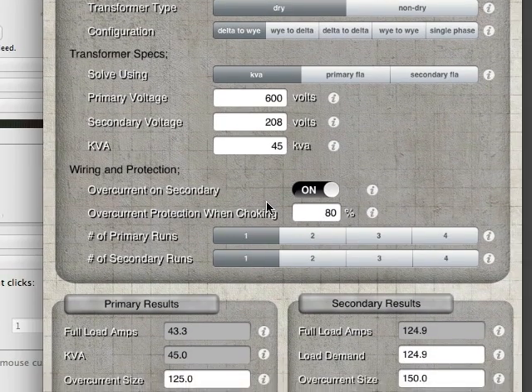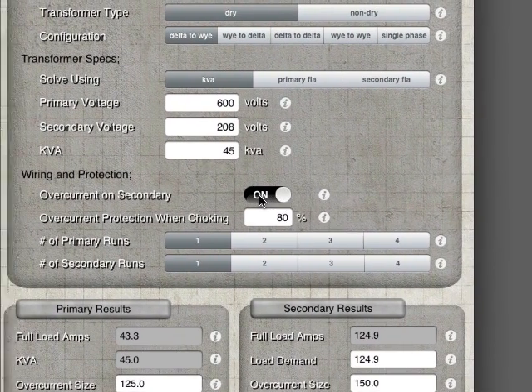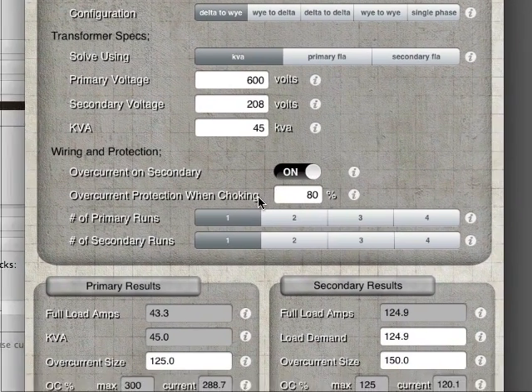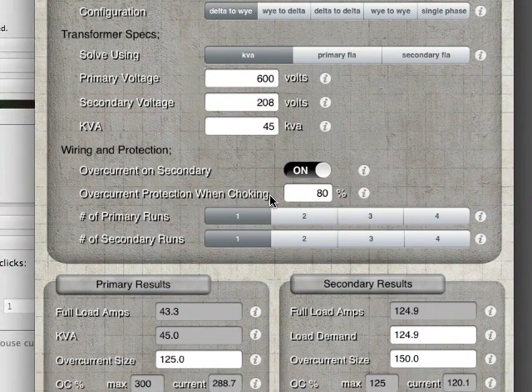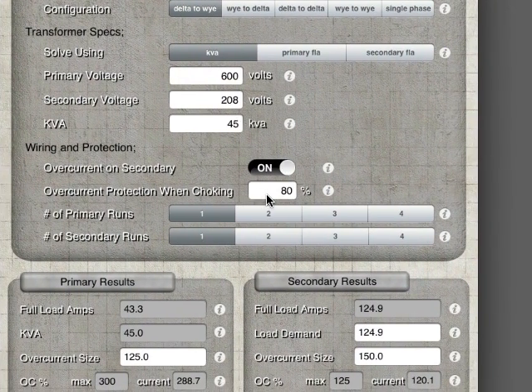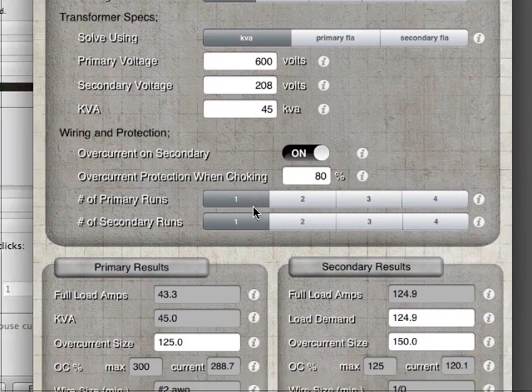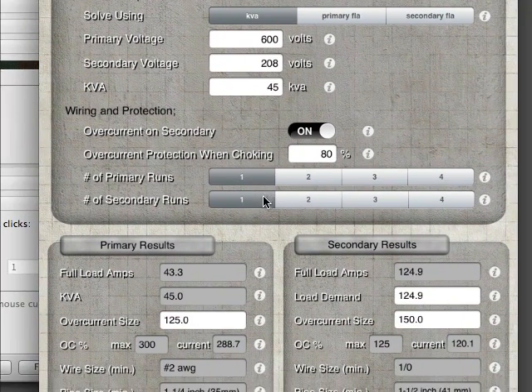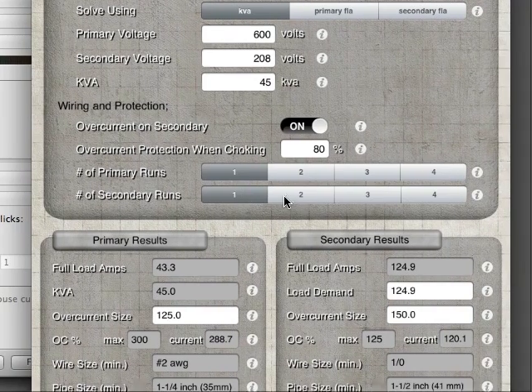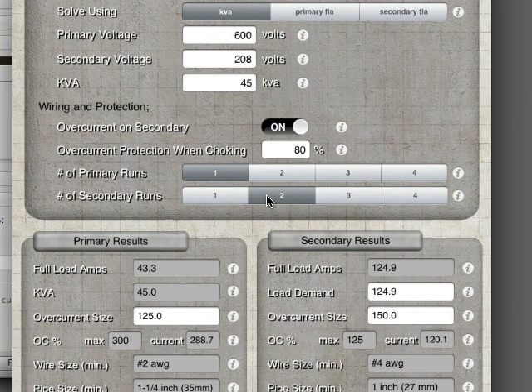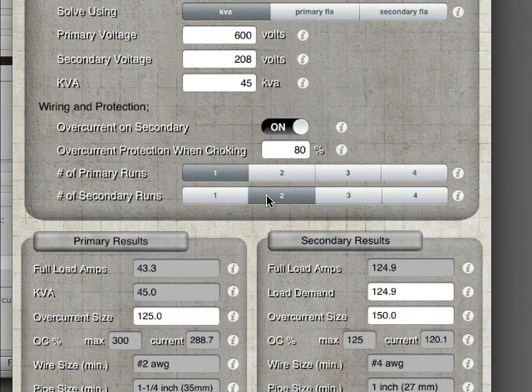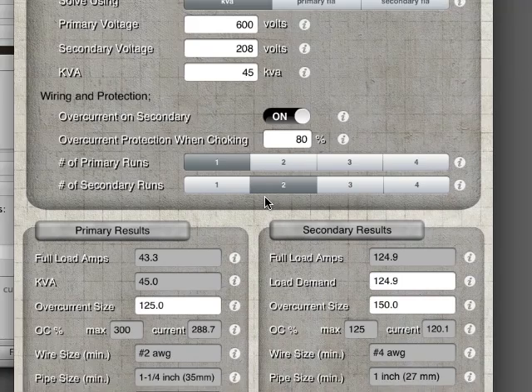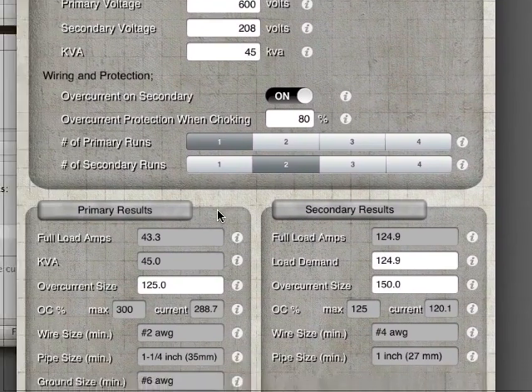You can turn your secondary protection on or off, so for now we'll keep it on. You can set your overcurrent protection when choking, so we're going to protect that 80%. And then you can set your number of runs, so sometimes you might want to put a parallel run in your secondary because your wire size is too large. So let's say we're going to do that today. You can do up four runs on either.